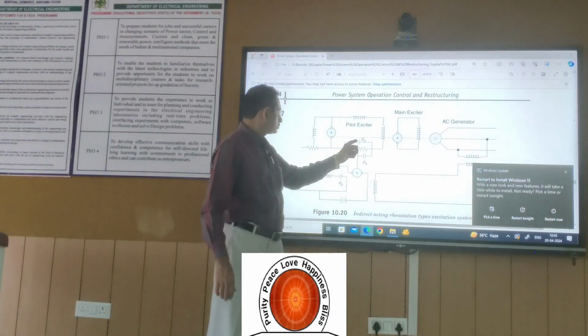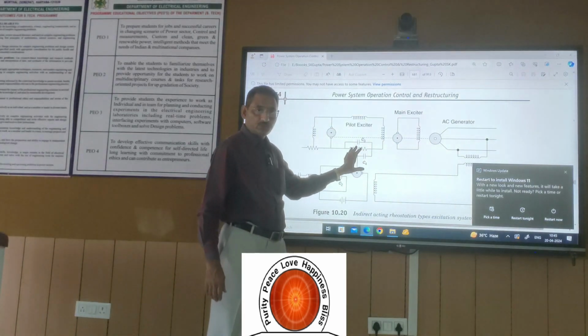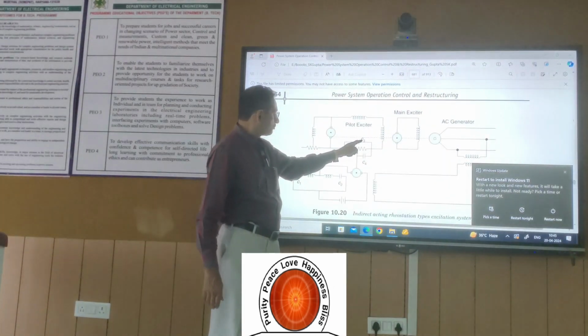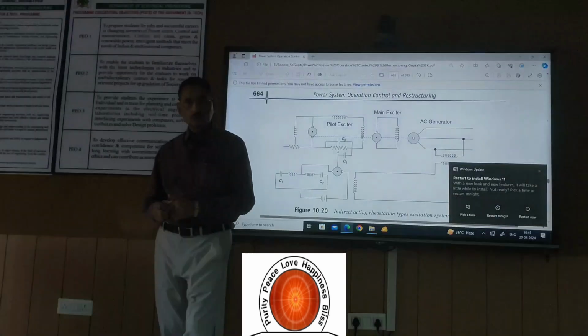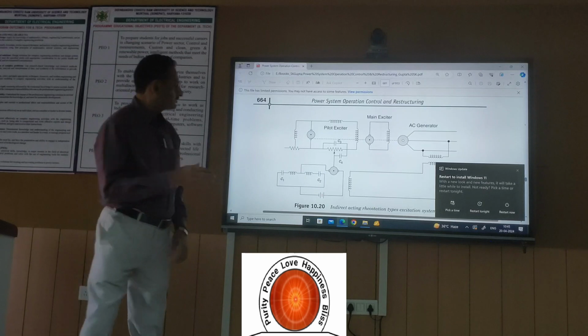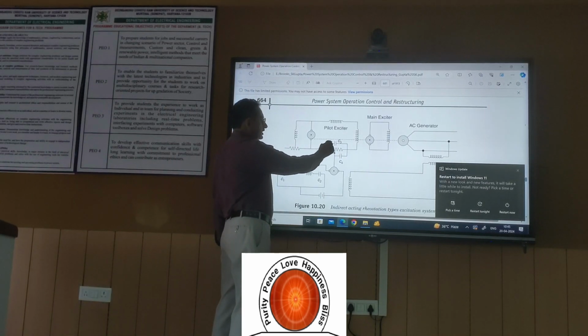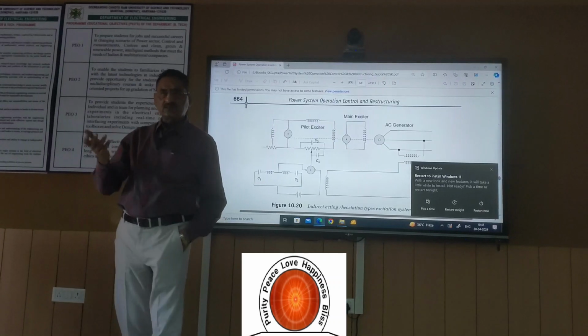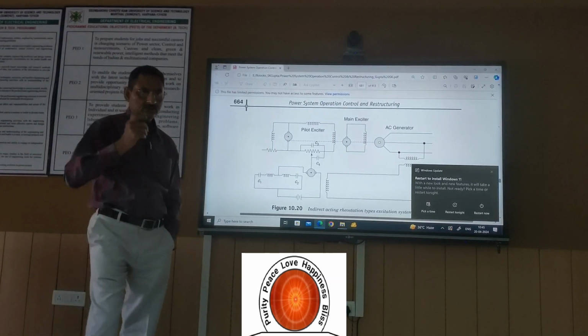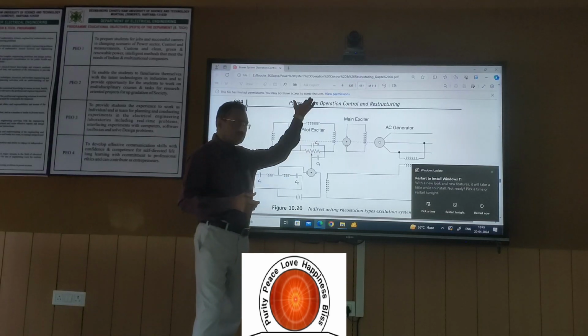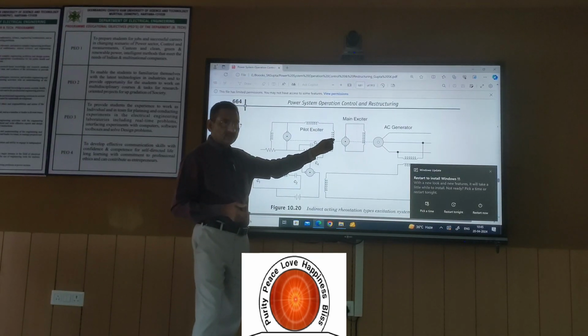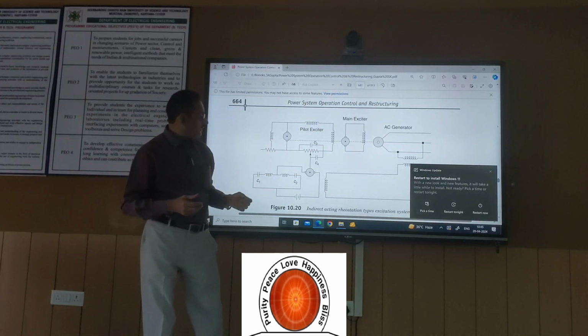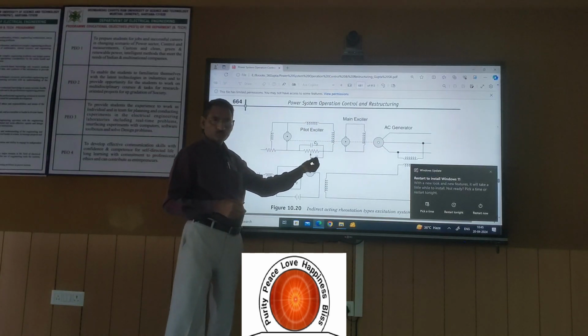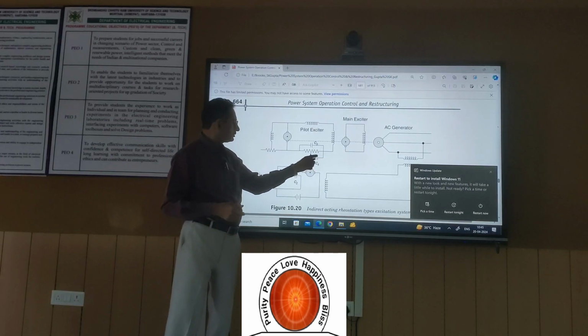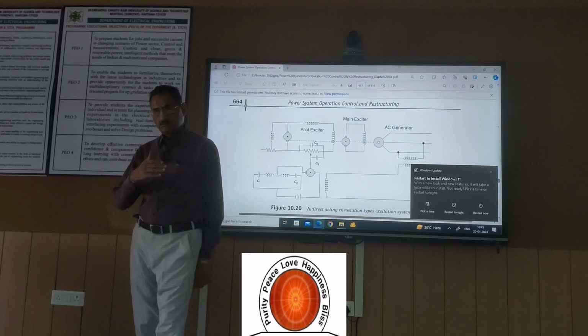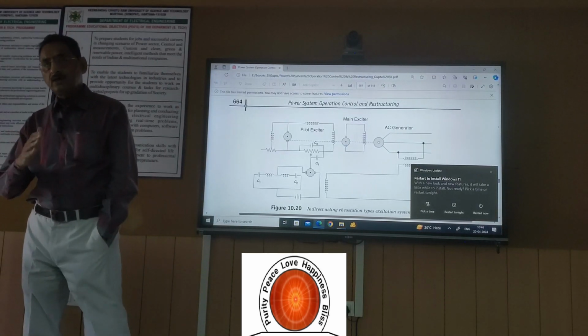If the voltage deviation is high enough, more than say 20%, at that time instead of the gradual method, contactors C3 and C4 will be closed and operated directly. If C3 operates, the whole resistance is bypassed, so current will immediately increase. When current increases, speed will increase and voltage will be improved. Otherwise, if C4 is directly bypassed, half of the resistance will be closed. So in case of a large gap, this direct method is used.